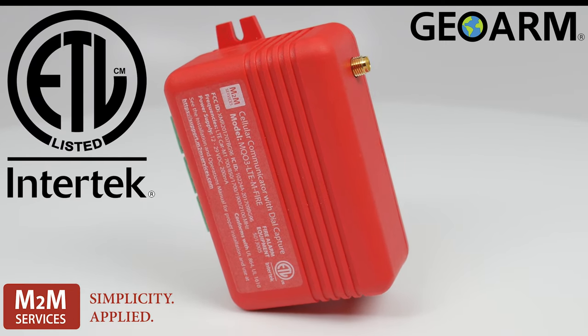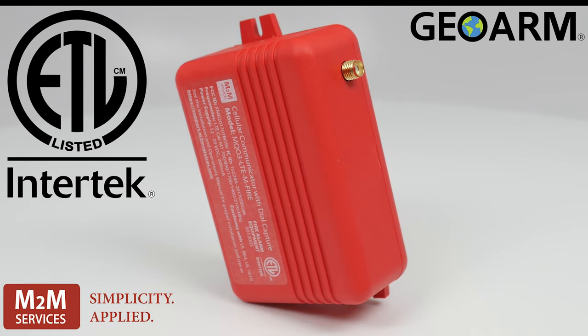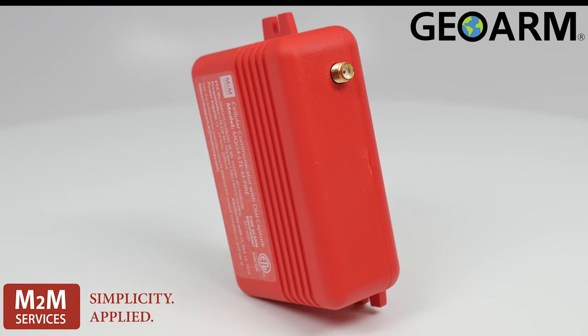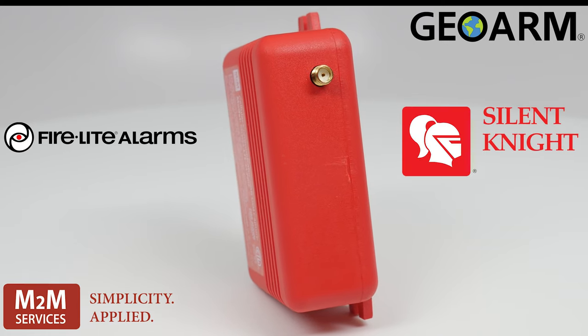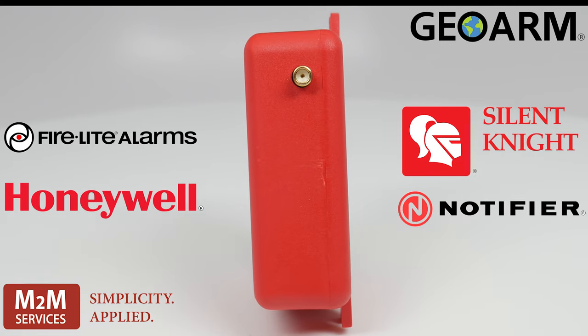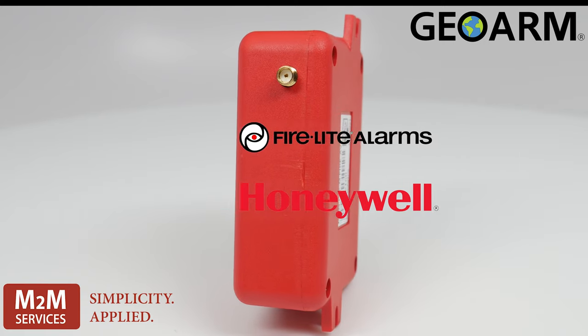This device is a dial capture interface supporting Contact ID and SIA reporting formats. With reporting times as low as 20 seconds, this device is supported on panels such as Fire-Lite, Silent Knight, Notifier, Honeywell, Potter, and any other fire panel that supports Contact ID or SIA reporting formats.